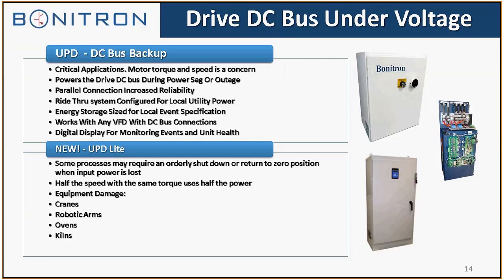If you are making nuts and bolts or something that doesn't have a high downtime cost or product damage cost, that's probably not a good application for ride-through. We look for critical applications that can have no change in speed or torque of the motor. Even though the drive has some ride-through capabilities, it will only ride through very short events, usually cycles only. But you may have a flow sensor or chill water flow going to a machine tool down the line, and in critical applications there's much more precise monitoring of exhaust air and chill water and things that are feeding the process.